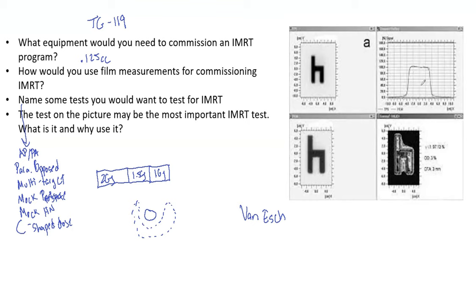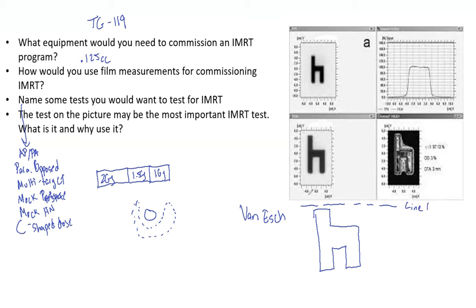You can highlight different profiles and look at the dose. Line one shows an area of no dose — above the chair, where the MLCs are covering everything — so you can verify the interleaf leakage and the intraleaf leakage. The chair itself is the dose that is getting through and everything else is covered by the MLC.